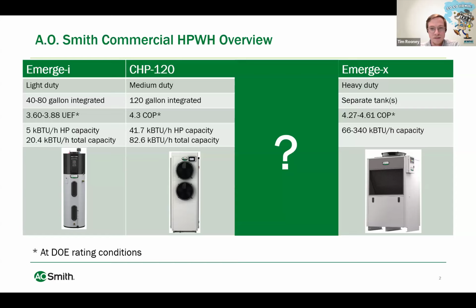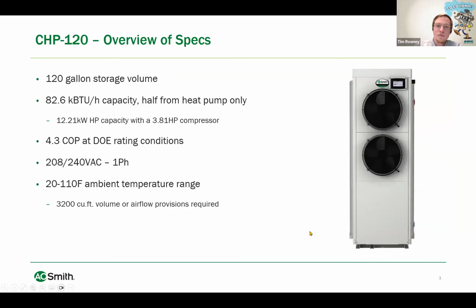And like I said, we'll come back to this hidden third cell a little bit later in the presentation. I think that the basic specifications of the CHP 120 have been shown a few times already today, so I'm not going to spend too much time here. But just a few highlights: in hybrid mode, there's about 83,000 BTUs of total capacity, and about half of that is available from the heat pump itself. And I think this was also shared earlier that there's a 4.3 COP when measured at lab DOE test conditions. It is available in both 208 and 240 volt AC with single phase. I also do want to highlight that there is a 3,200 cubic foot room volume requirement for this product.